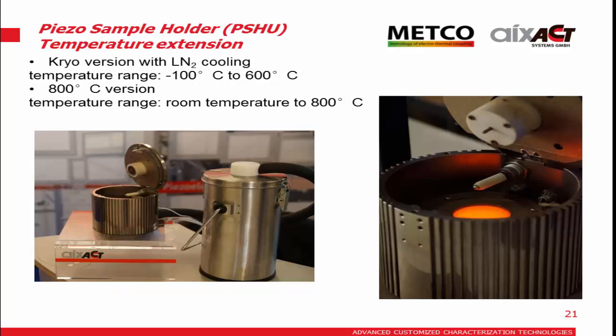So within this project we developed the higher temperature capabilities. So we had a version from -100 degrees C to 600 degrees C, and the main limitations are actually the materials that you can use. So for going to high temperatures, you must have a material which still establishes a good contact over the whole temperature range without degradation. And if you put in the sample and pick it out, you must not deteriorate your setup, so being able to measure many samples without destroying the electrode materials. And at 800 degrees C, you can see that it's already nicely glowing in this case.